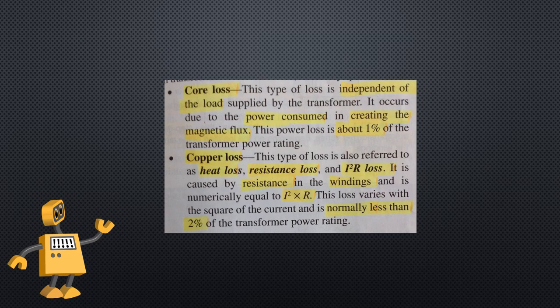Transformer efficiency. Transformers are highly efficient but do have some losses due to heating and power consumption within components. Two kinds of losses are inherent: first, core loss, which is independent of the load and caused by power consumed creating the magnetic flux—about 1% of the transformer power rating. Second, copper loss, also referred to as heat loss, resistance loss, or I²R loss, caused by resistance of the windings. This loss is numerically equal to I² × R, varies with the square of current, and is normally less than 2% of the transformer power rating.